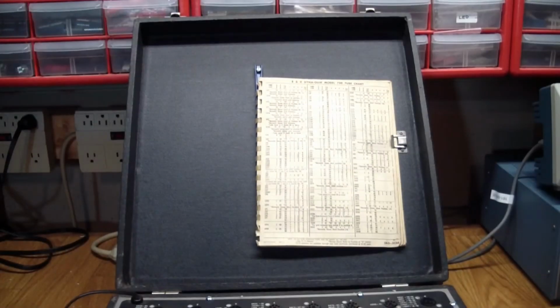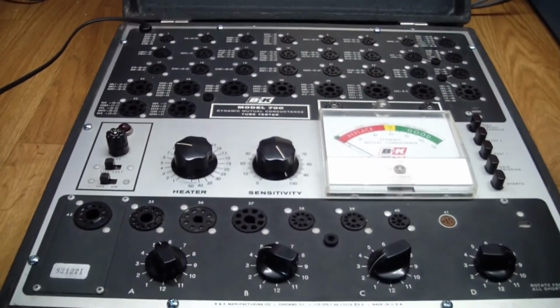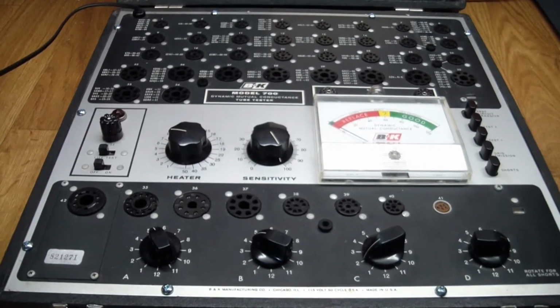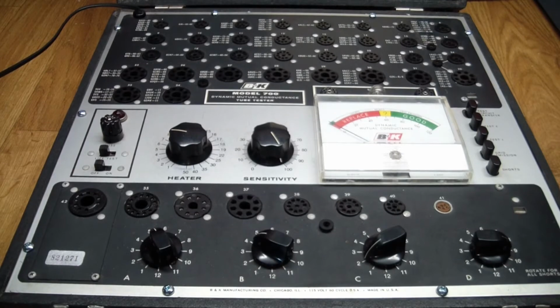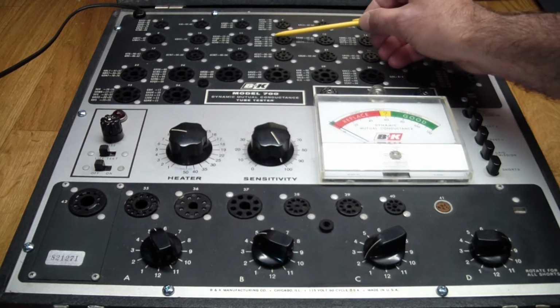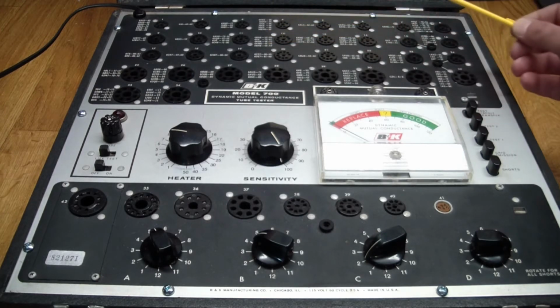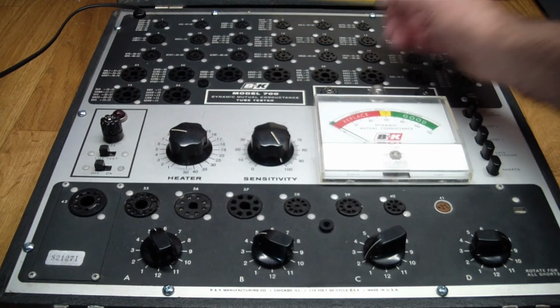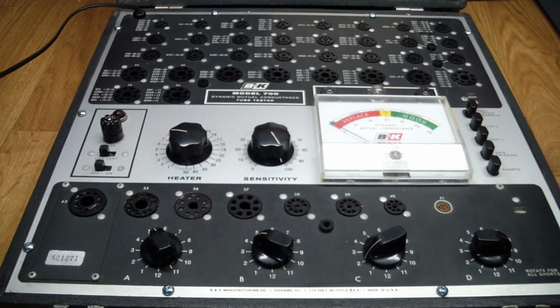One of the nice features of this is, remember it had the words Dynaquick in its name, and the Dynaquick part refers to the upper portion of this, where there are 34, 35, 36 sockets, and these sockets have the names of the tubes that they'll test right next to them, and also the sensitivity adjustment. You only have to plug the tube into the right socket, adjust the sensitivity, and then look at the oversized meter to tell you what shape the tube is in.